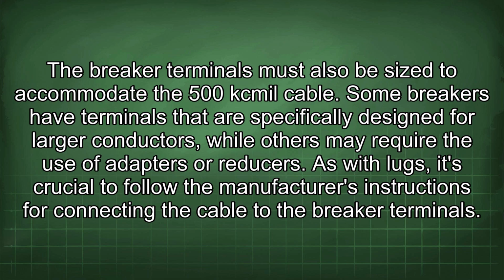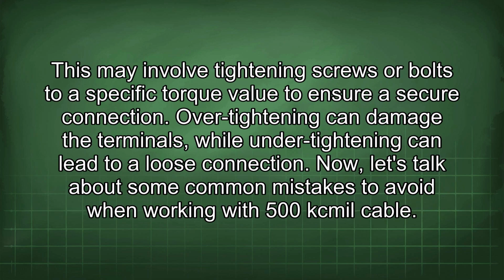Some breakers have terminals that are specifically designed for larger conductors, while others may require the use of adapters or reducers. As with lugs, it's crucial to follow the manufacturer's instructions for connecting the cable to the breaker terminals. This may involve tightening screws or bolts to a specific torque value to ensure a secure connection. Over-tightening can damage the terminals, while under-tightening can lead to a loose connection.